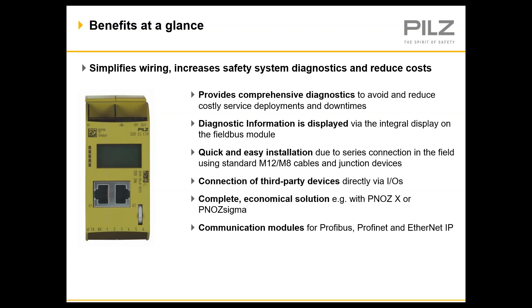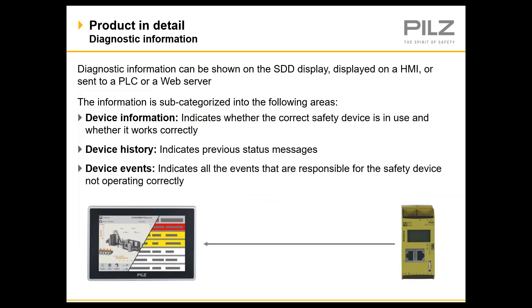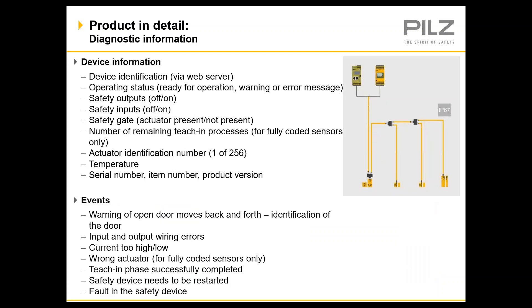Finally, highlighting the last bullet point, the SDD can communicate to third-party PLCs using listed protocols. Using these PLC protocols, we can transmit diagnostic and status data to a PLC or an HMI. Those data types can provide information on the device itself, the operating status, the history of any previous status messages, and any current issue that is causing the safety device not to operate properly. Listed here is the specific information obtainable through the system, divided into device information and event information: what device is it, what is the current operating status, what are the statuses of the safety outputs and inputs, are there wiring errors, and is the safety device faulty.